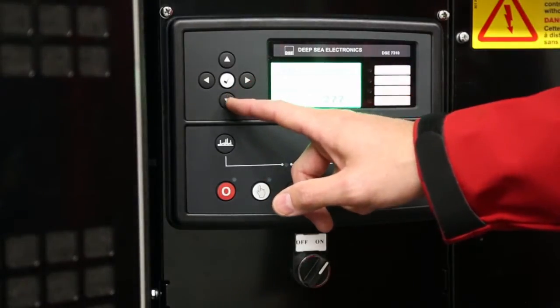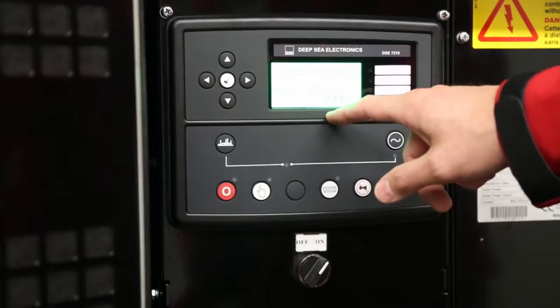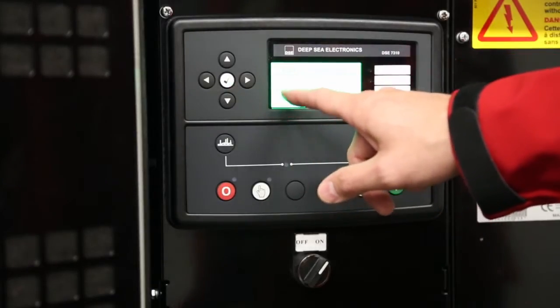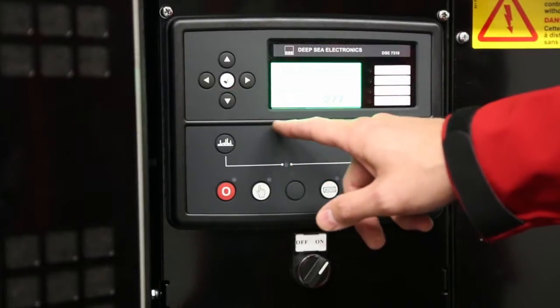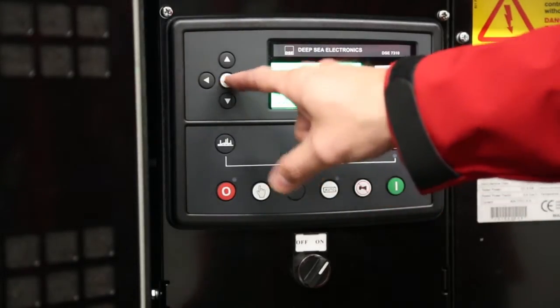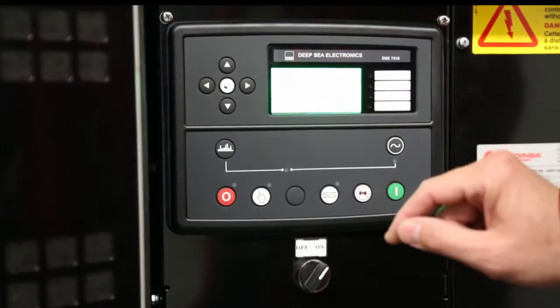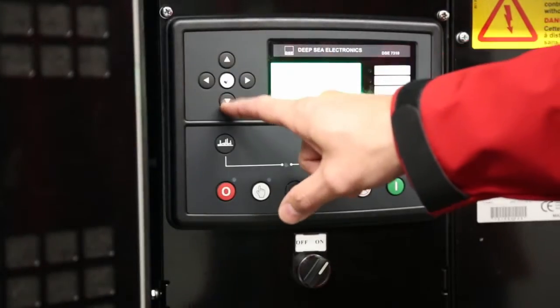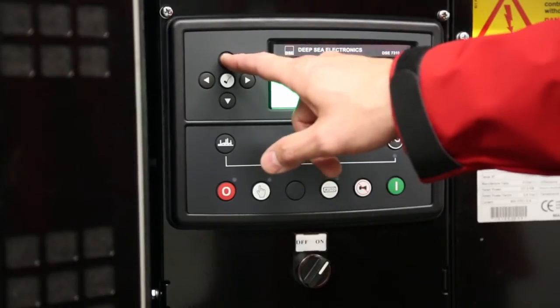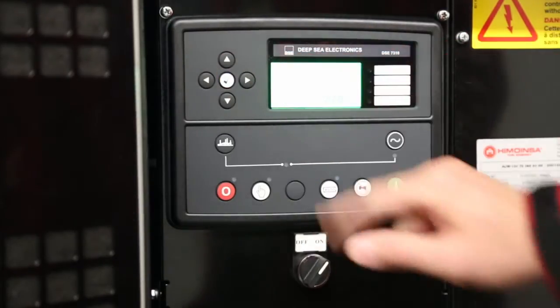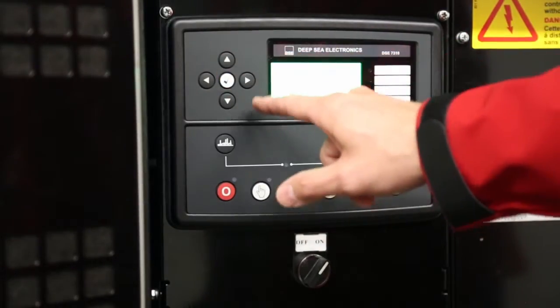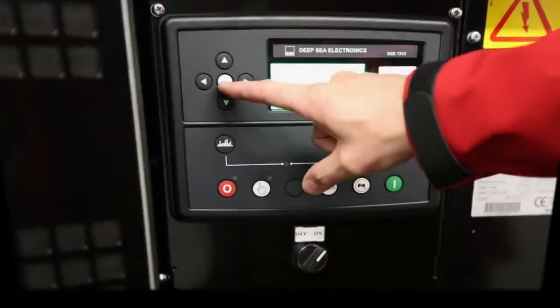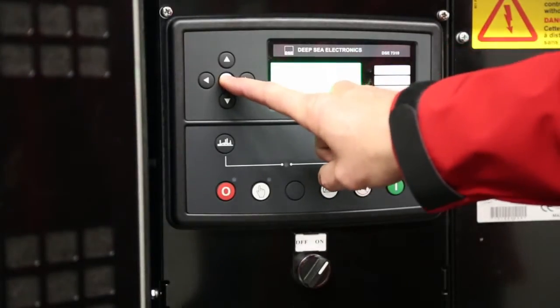Note the voltage parameters are showing single phase sensing. If you need to change your nominal voltage, press the white check mark button and the voltage parameters will flash. Press the up or down button depending on what you need to change it to. Hit the white check mark button and then continue adjusting parameters as needed.